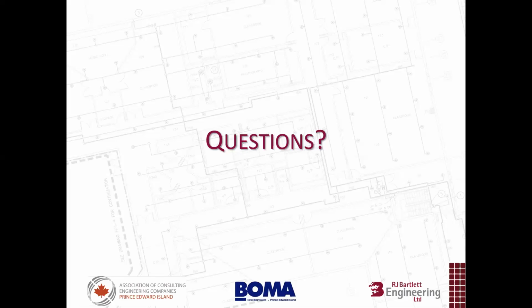You can't have more than one 15-second delay in an egress route, correct? Yeah, that's right. Sorry, you can have more than one delayed egress door or door hardware, but the cumulative time is what matters. For example, if I had two of these doors between me and an exit, one could have 7.5 seconds and the other one could have 7.5 seconds of delay, but they wouldn't be able to be 10 and 15, or 15 and 15. Okay, that was the follow-up question to that. Thanks. Yep.